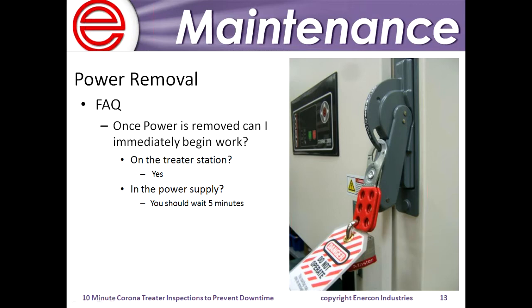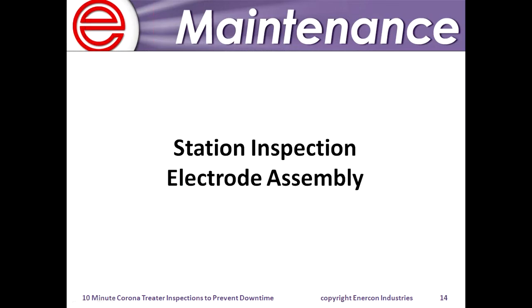If you're going to work inside the power supply, just opening it up to check inspections, you'll definitely need to make sure the power upstream is locked out. Also, you should wait 5 minutes for the power supply to completely de-energize. So that's the information on that.